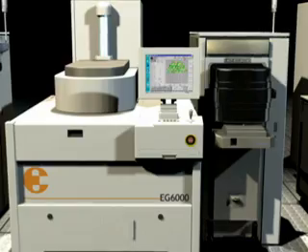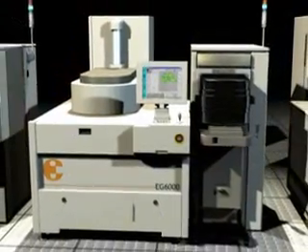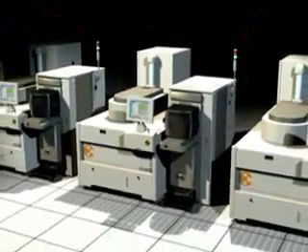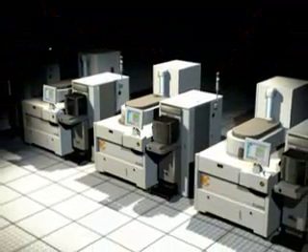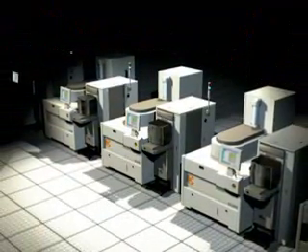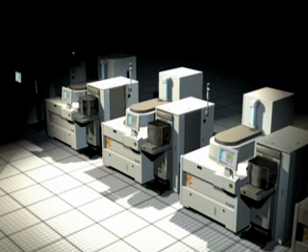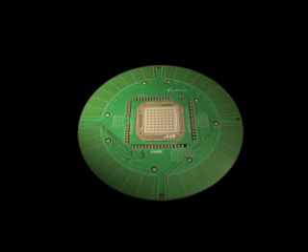Electroglass's primary product is the wafer prober. Wafer probers work in concert with automatic test equipment and probe cards to test devices prior to packaging. The automatic test equipment has the electronics and power supplies needed to activate the devices on the wafers for electrical test.